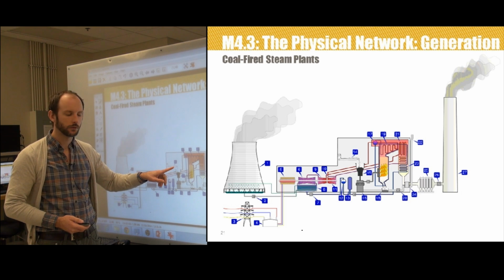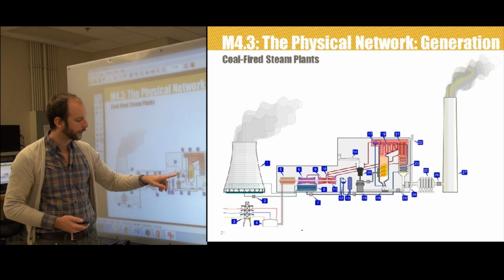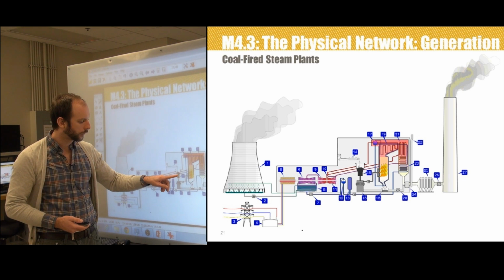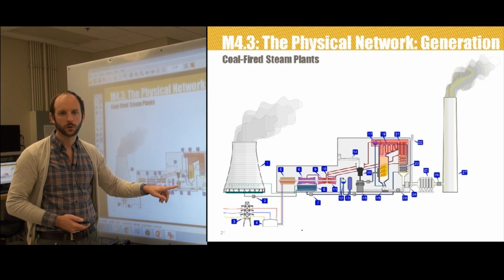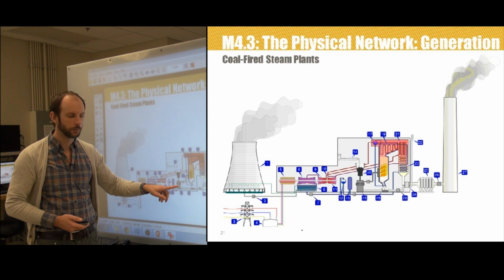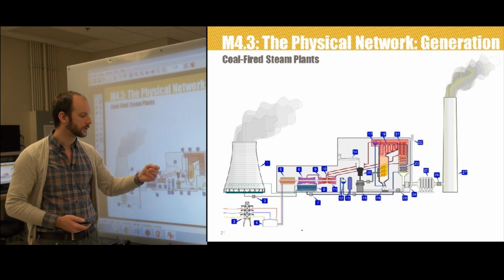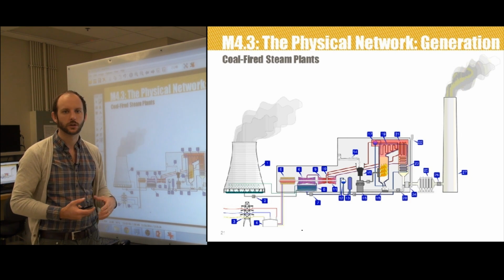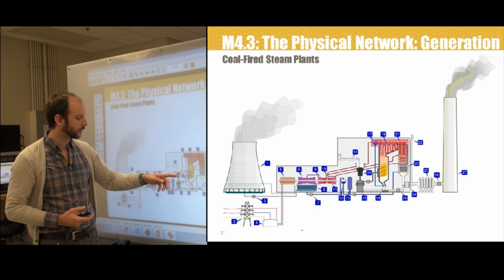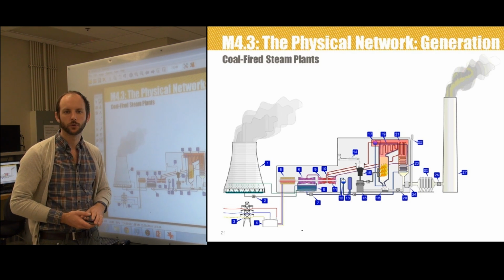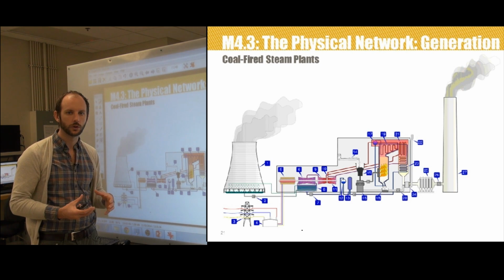It's being drawn from these external coal stacks. And then it falls into a hopper, a two-stage process where there's a hopper and then what's a pulverizing fuel mill. And what these do is they take these chunks of coal and they turn it into coal dust. So 15, the hopper, and 16, the pulverizing fuel mill, convert these chunks of coal into coal dust.